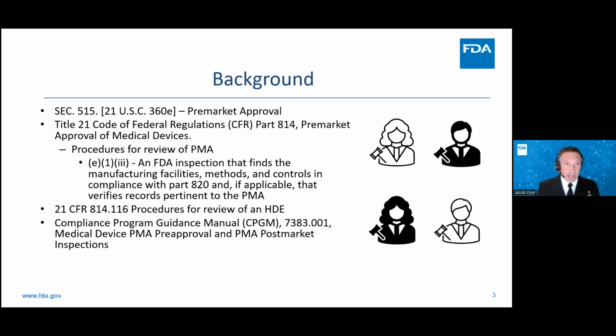So 814 is going to cover pre-market approval of medical devices. It's going to have the procedures for review of PMA. It's going to have that with the FDA inspections in compliance with 820. And then it also has provisions for HDE devices, which we'll talk about a little bit, and that's in 814.116. And then there's the compliance program manual, which guides the PMA pre-approval and then the PMA post-market inspection. And we'll talk a little bit more about what those would be.